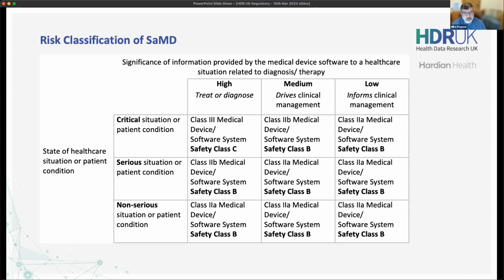And this is what everyone should be doing. Then what the EU says is there's a classification scheme where we call devices class 1 in Roman, class 2A, class 2B, class 3. The US system is slightly different. They call it class 1, class 2 and class 3 and often use Arabic numbers, not Roman. So that's how you can sometimes tell subtly whether it's a US or an EU/UK classification.